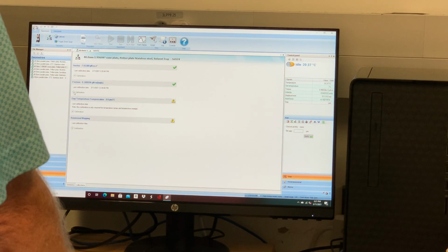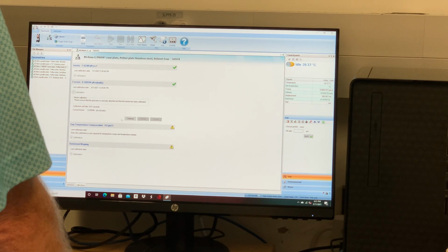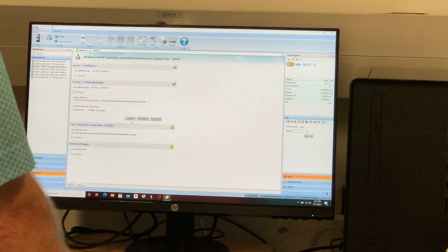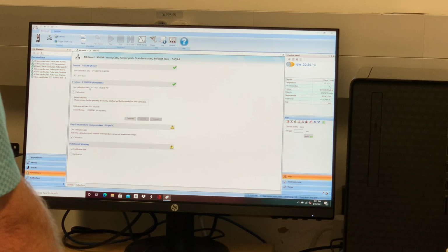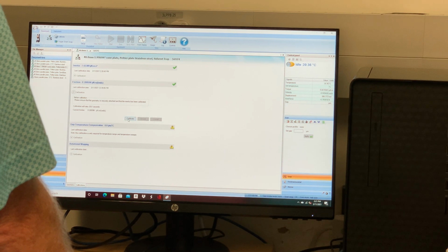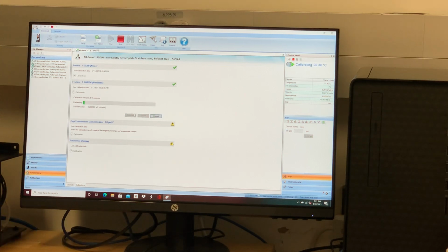The second calibration here is the friction calibration. Again, it takes 30 seconds. Typically, it's from 0.27 to 0.3 as a value. Hit calibrate. And what it's going to do, it's going to spin the geometry and correct for any friction.